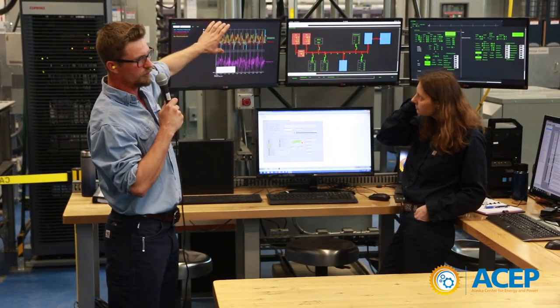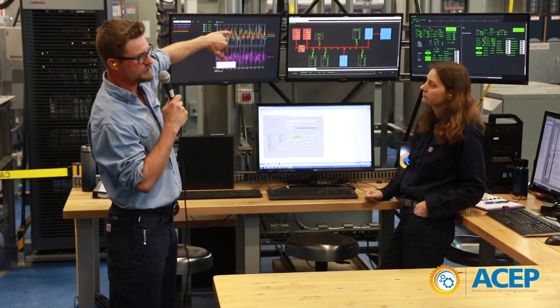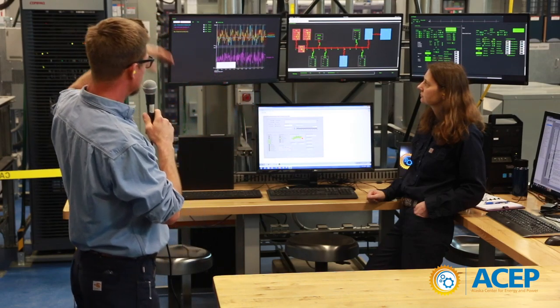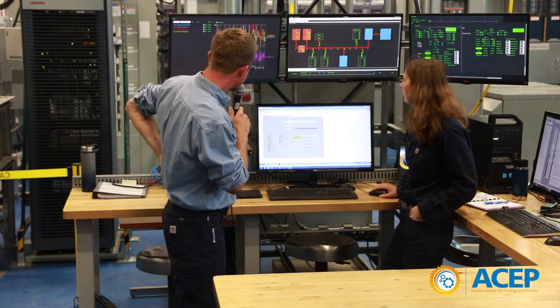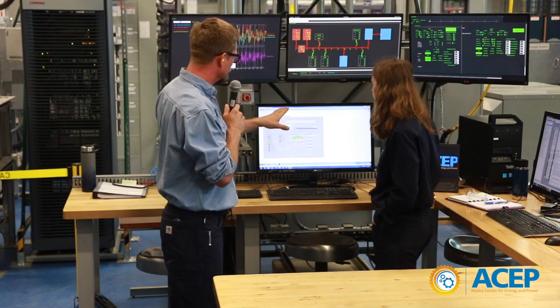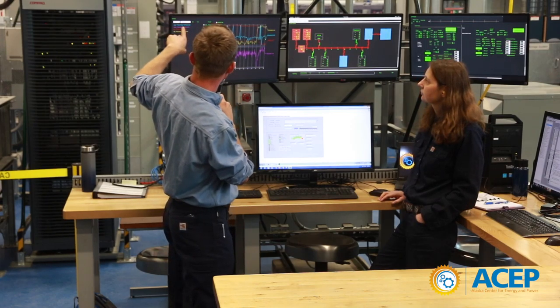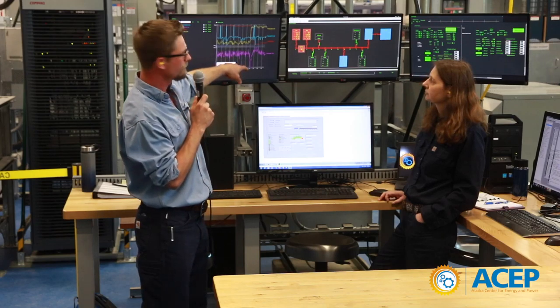The lines all have their own scaling, so you can't necessarily compare them in terms of magnitude. The generator is making up the difference between the load and the wind power. Our load is 100 kilowatts. We just increased our wind power — the yellow line went up, our generator output went down, and the inverter output dipped slightly.